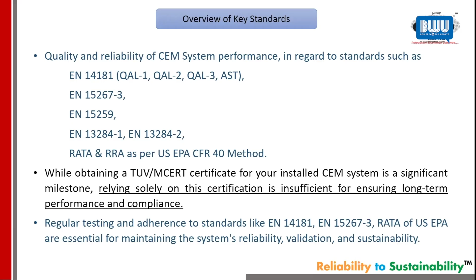Now, continuous performance reliability. See, any measuring equipment, whether a small multimeter in your laboratory or a digital scale or any other thing, you need to ensure that it is properly tested and the measurement you are getting is reliable. Maybe there is a tolerance, but it should be a defined tolerance. There may be a drift, but it should be a defined drift. You must know what the drift is. So regular testing, particularly as per the QAL 2, AST protocols, RATA, ensures that the system continues to operate reliably.